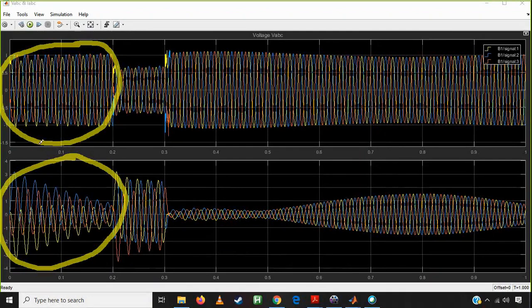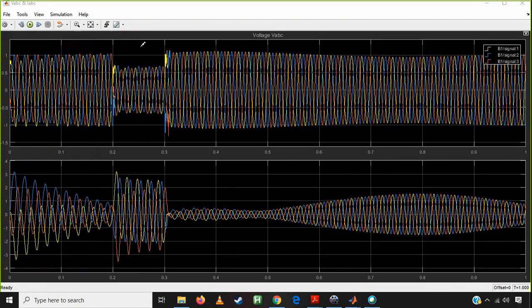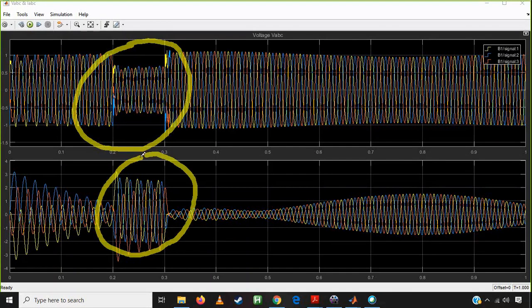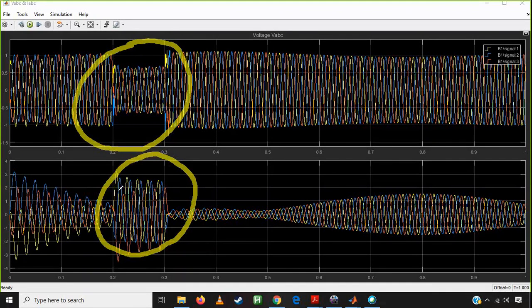At 0.2 seconds, the fault occurs. If you look at the voltage and current: the voltage is going to drop towards zero when there is a fault — it will be reduced but not to zero. The current is going to increase significantly. It is near about 1 per unit normally, but during the fault it is going to be huge. The transient current is going to increase sharply.